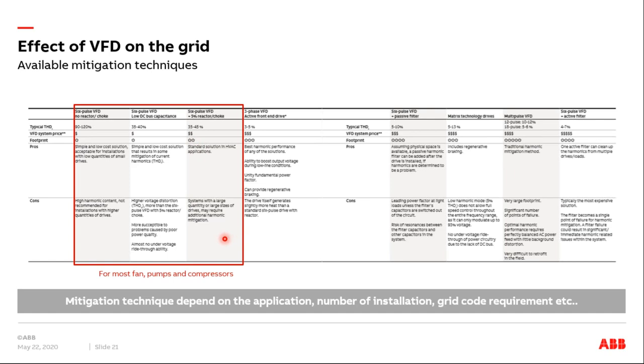But if you are using larger motors and it's a larger system, maybe the grid operator would want you to have even more mitigation. So you want to go to active front end. For example, you could go to multi-pulse VFDs, where you are using 12-pulse or 18-pulse rectifiers. So there are different ways of mitigating this. It's just a matter of cost, and as you know, customers would only do it if they are required to. So if the grid really asks them to make their harmonics, let's say, below 5%, then they have to do it, and they will use active front end, for example. But if they are not required by some standards or the grid, then normally you would go for the cheapest option. And as I said, this reactor is one of the most common ways of mitigating this issue.